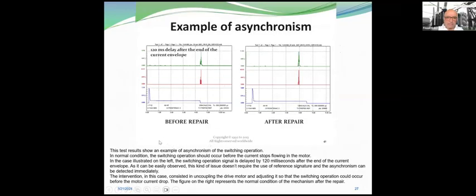Example of asynchronism. This test result shows an example of asynchronism of the switching operation. In normal condition, the switching operation should occur before the current stops flowing in the motor. In the case illustrated on the left, the switching operation signal is delayed by 120 milliseconds after the end of the current envelope. As can be easily observed, this kind of issue doesn't require the use of a reference signature, and the asynchronism can be detected immediately.